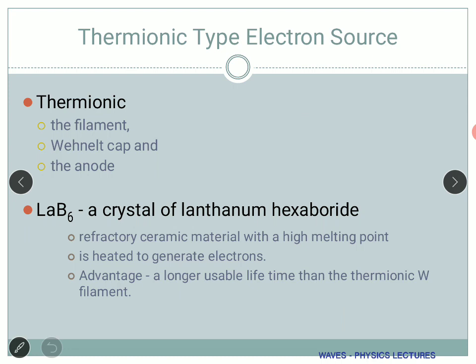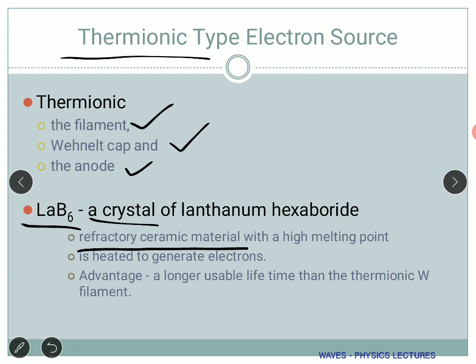There are two types of electron source: one generated using temperature, called the thermionic type. Any electron source has three main parts: the filament, the Wehnelt cap, and the anode. Lanthanum hexaboride is a thermionic type electron source — it is a refractory ceramic material with a very high melting point, so even at very high temperatures it survives. It is heated to generate electrons, and its advantage is a much longer usable lifetime compared to the tungsten filament.